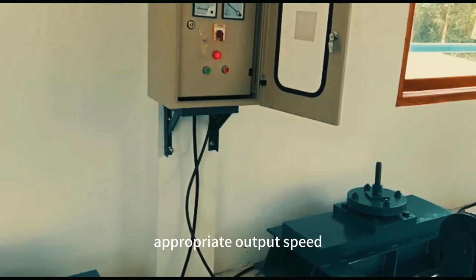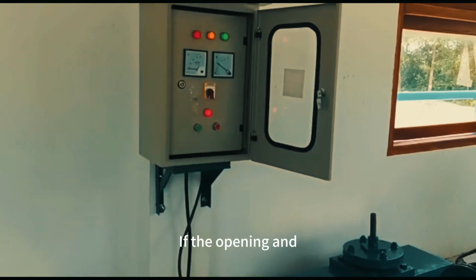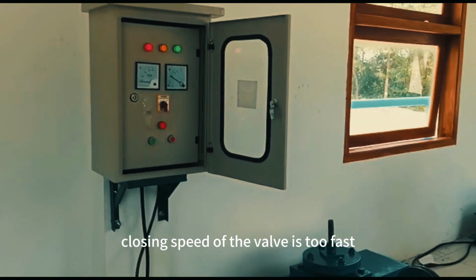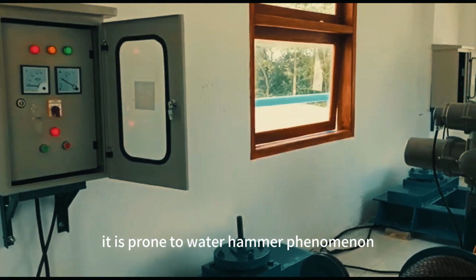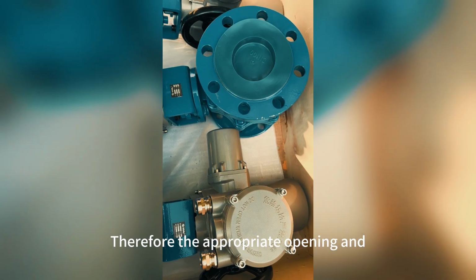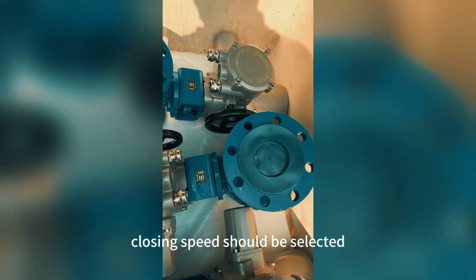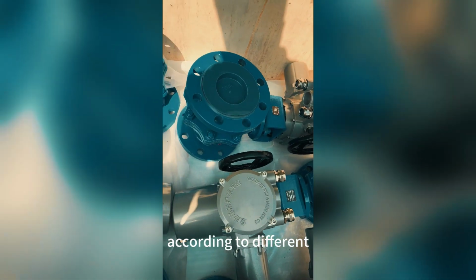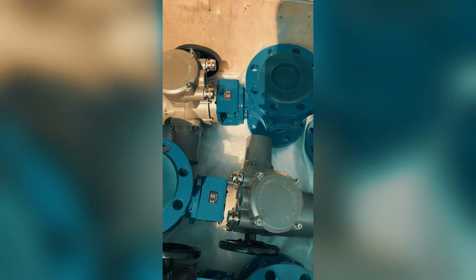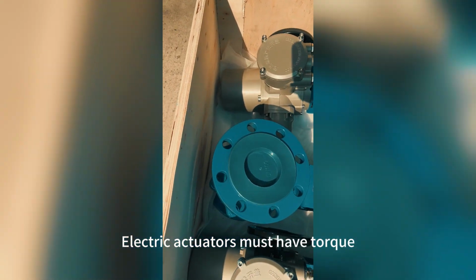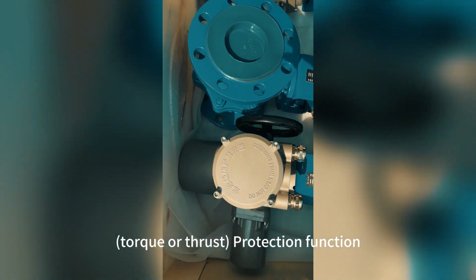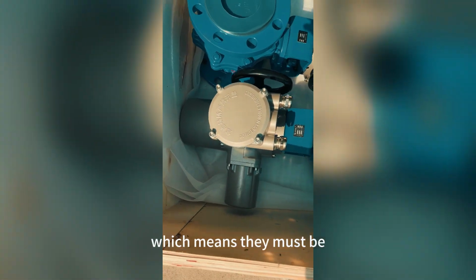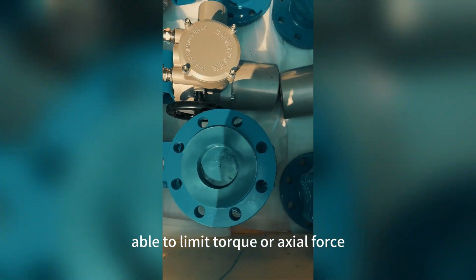Appropriate output speed. If the opening and closing speed of the valve is too fast, it is prone to water hammer phenomenon. Therefore, the appropriate opening and closing speed should be selected according to different usage conditions. Electric actuators must have torque or thrust protection function, which means they must be able to limit torque or axial force.